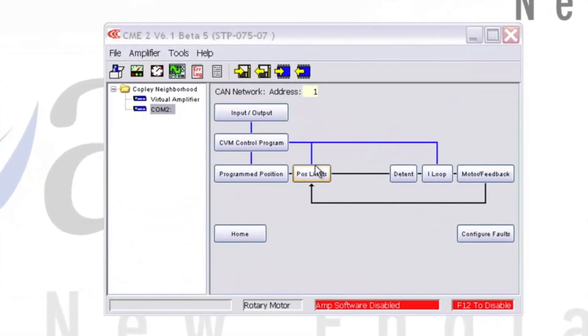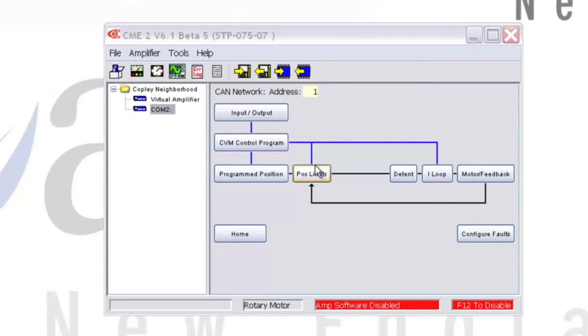At this point, the drive should be fully configured to test run the motor. One additional change we need to make is to ensure that our I/O is configured so that the drive is hardware enabled by default. This is only for testing purposes, so in a normal scenario, you'd have another circuit wired into Input 1 to control whether the drive is enabled or not.